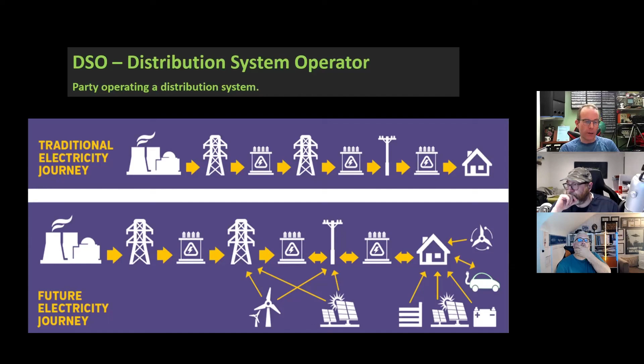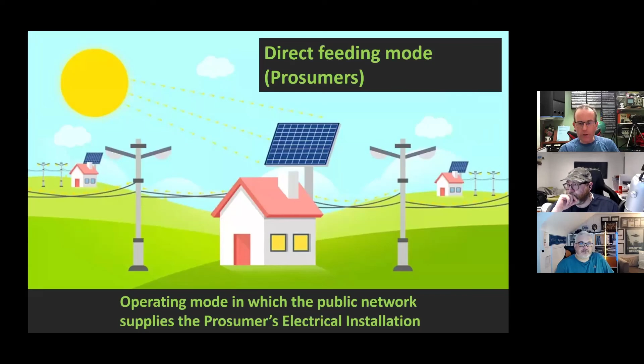There's a comment a while back from Jake Bennett regarding rebar earthing, asking: will the installation be TT rather than TNCS or TNS, or is this in addition to DNO earthing? The deal with foundation electrodes is that it's in addition to what the DNO has provided. So it'll be a TNCS supply to your property, and then the foundation earth electrode is connected to that, providing an additional path to true earth rather than just relying on what they're providing.